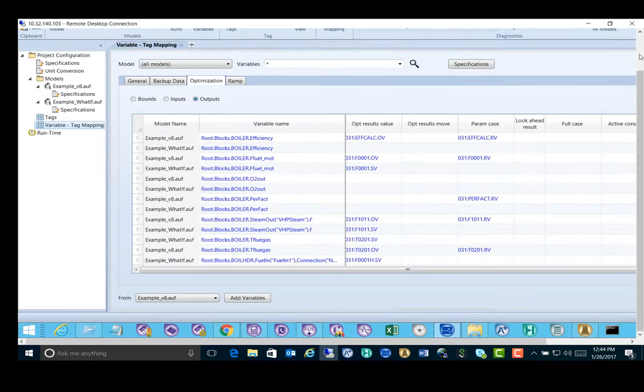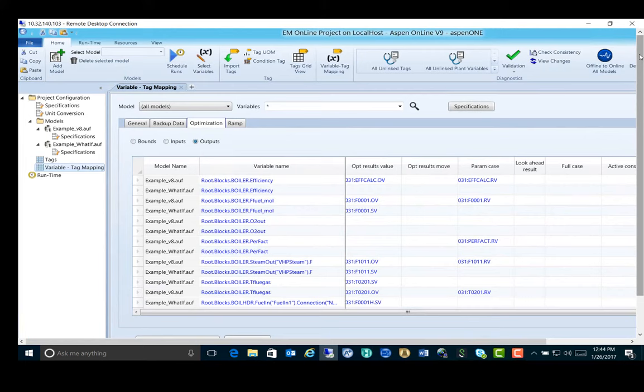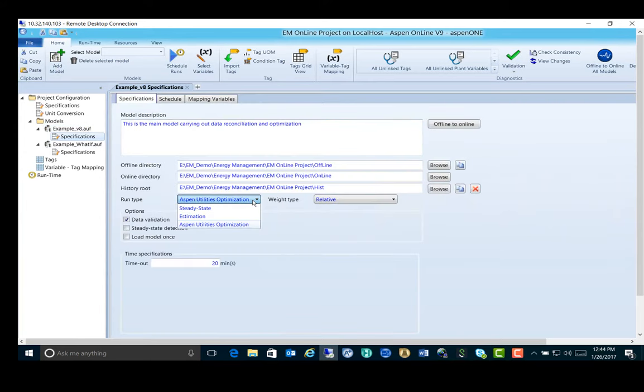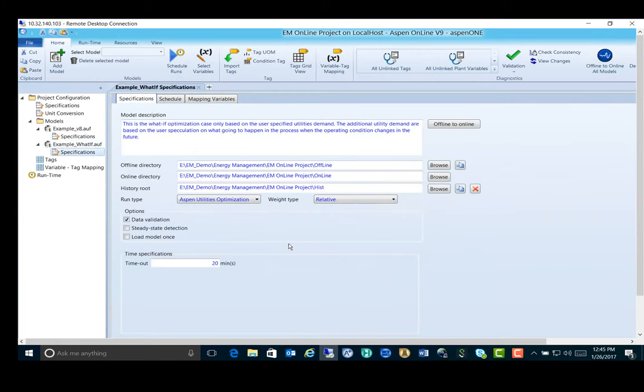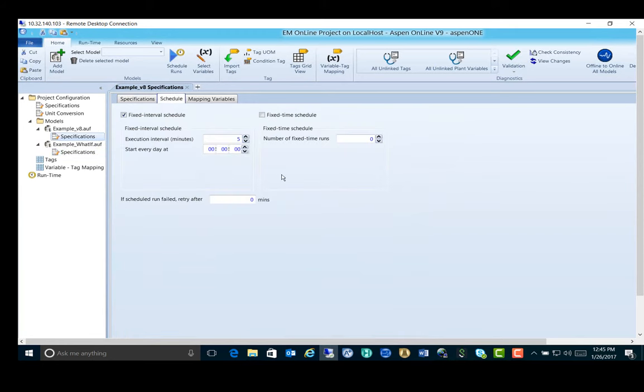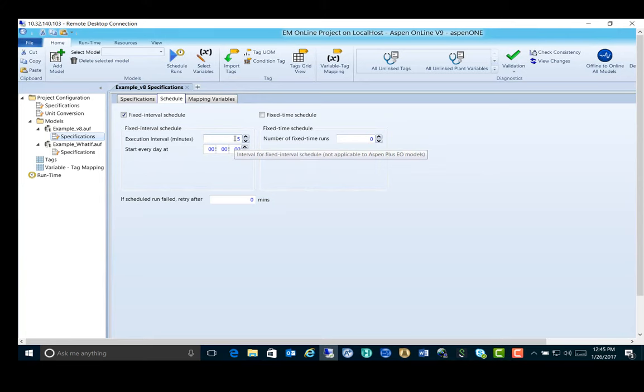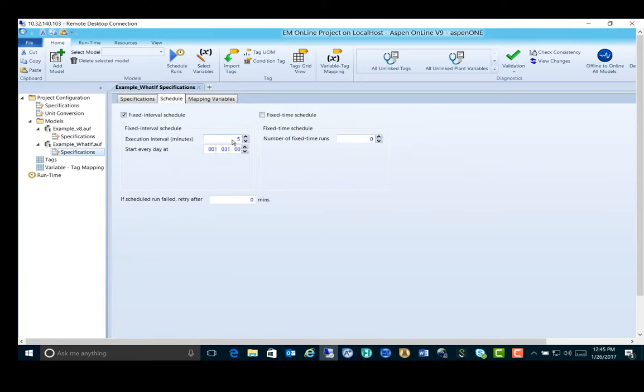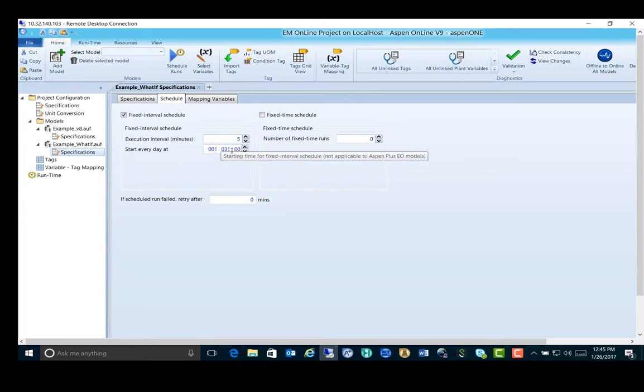This is the Aspen Online project to drive the utility planner model. As we can see, the two utilities models are included in the project. The first one is the main optimization model. It's specified as the full Aspen Utilities optimization, including data reconciliation run and optimization run. The second model is online what-if scenario analysis. It only includes optimization run. The two models are scheduled to run in a sequential order, every five minutes. If we switch to the schedule of the main model, it is scheduled to run on top of the hour, every five minutes. The second model is also scheduled to run every five minutes, but three minutes past the hour.